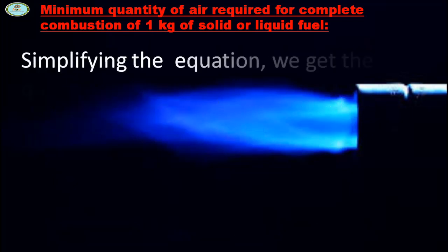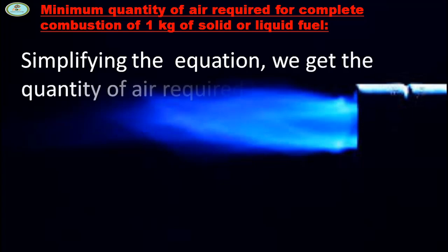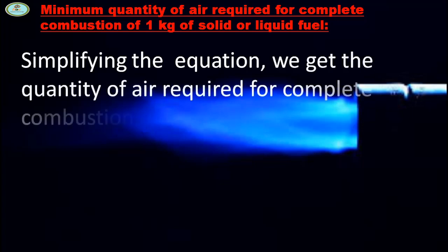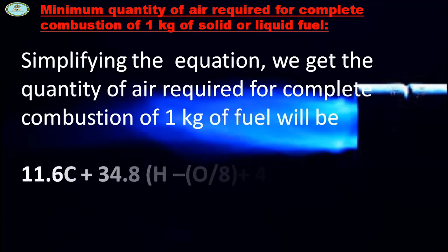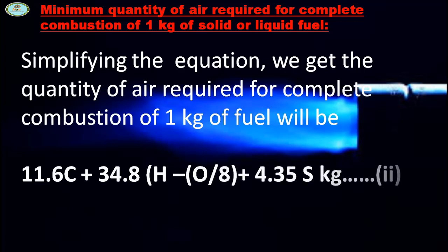Simplifying the equation, we get the quantity of air required for complete combustion of 1 kg of fuel as 11.6 C plus 34.8 into (H minus O by 8) plus 4.35 S kg.